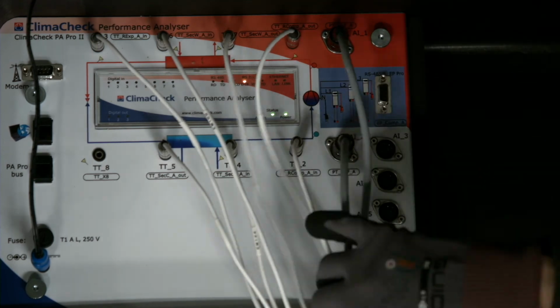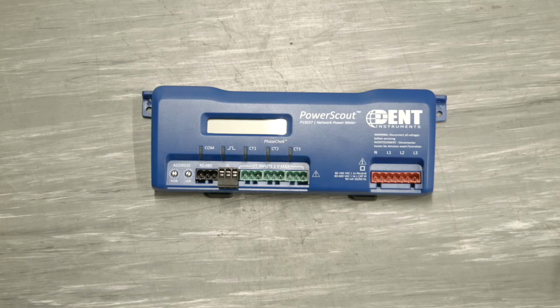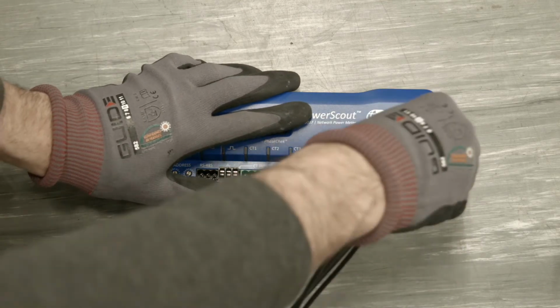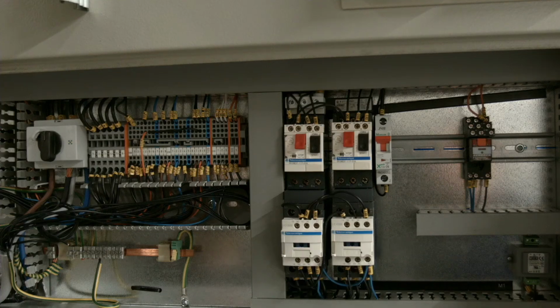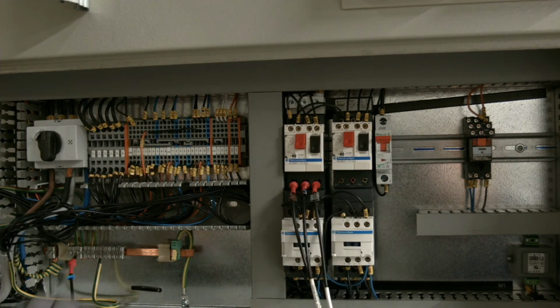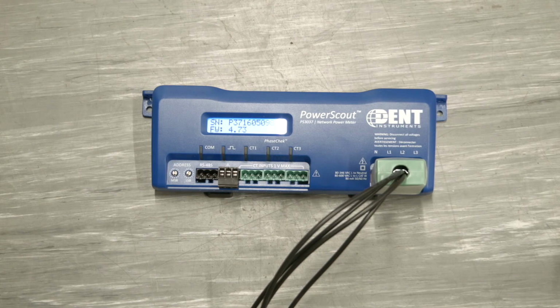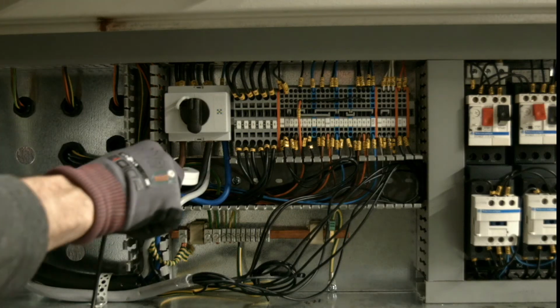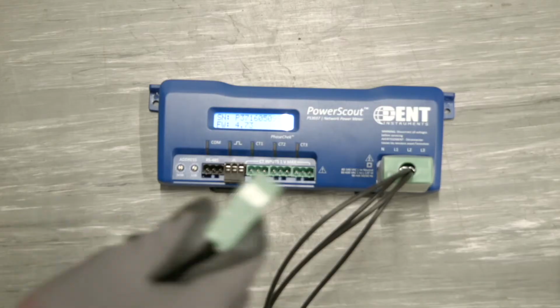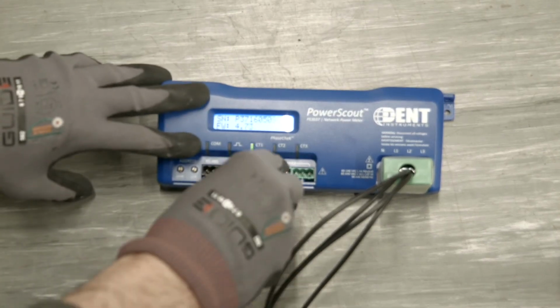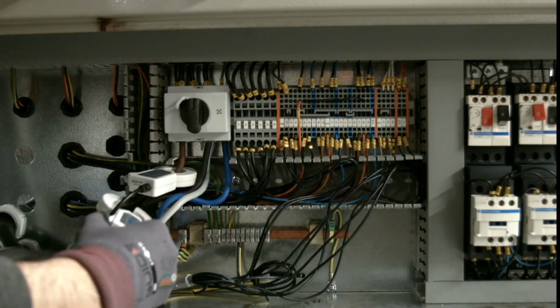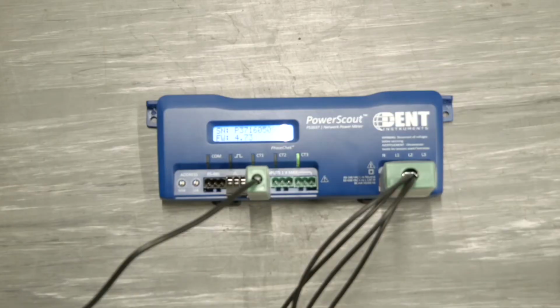Here is the power meter, 3-phase, does single phase, 3-phase with neutral, without neutral, any combination. Magnetic connectors quickly enable you to pick up the voltage. Plug this in. Indicator lights on the power meter will show you you're connecting your phases and your voltages correctly. Current clamps go around the compressor power input for a single compressor or a group of compressors.